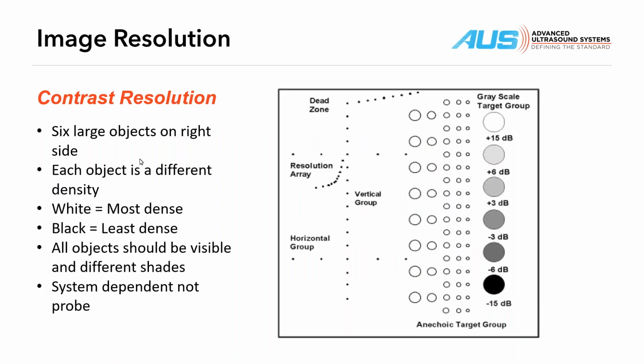Contrast resolution. Even the ACR accreditation doesn't specifically say you have to measure contrast resolution, but I find that it's one of those things that's very, very critical to measure. And in many cases, nobody ever checks it. When I check it on most ultrasounds, for example, this object, the -3 decibel, you can see they all have designations: +15, +6, +3, -3, -6, and -15 decibels. The -3 decibel one, for whatever reason in ultrasound, is the most difficult one to see.